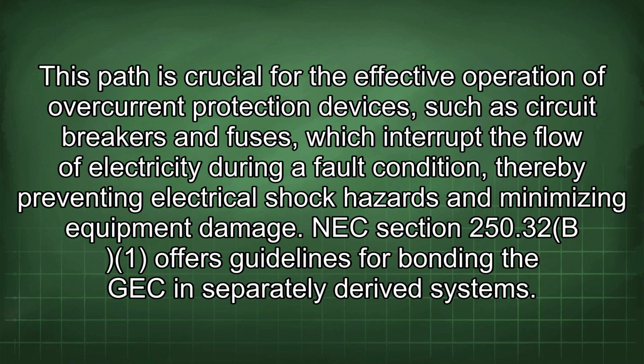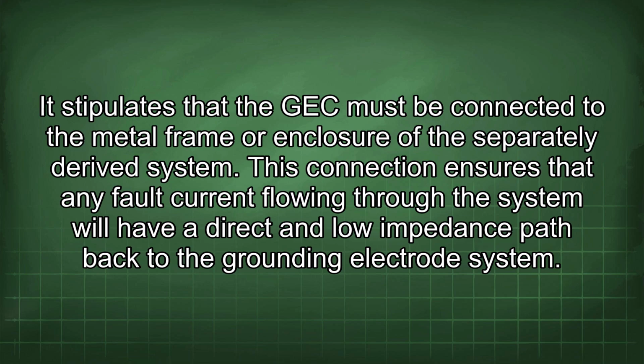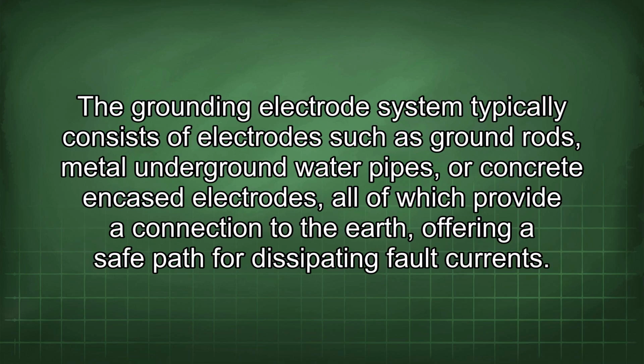NEC section 250.32 offers guidelines for bonding the GEC in separately derived systems. It stipulates that the GEC must be connected to the metal frame or enclosure of the separately derived system. This connection ensures that any fault current flowing through the system will have a direct and low impedance path back to the grounding electrode system. The grounding electrode system typically consists of electrodes such as ground rods, metal underground water pipes, or concrete encased electrodes, all of which provide a connection to the earth, offering a safe path for dissipating fault currents.